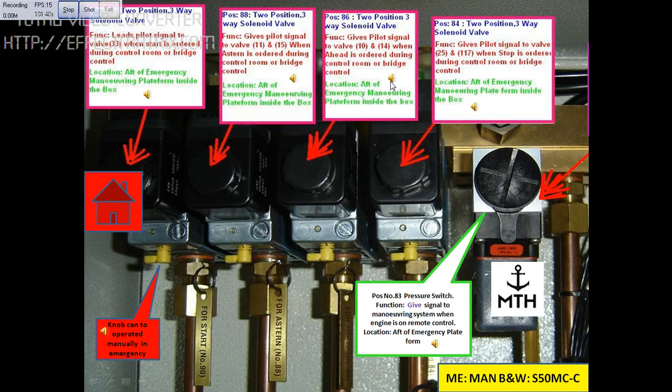This block is position number 86, which is a two position three-way solenoid valve. The function of this valve is to give a pilot signal to valve number 10 and to valve number 14 when ahead is ordered either from control room or from bridge control.